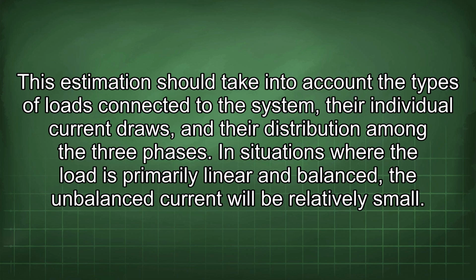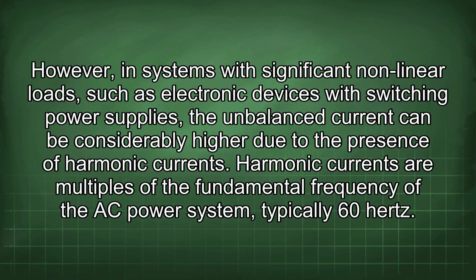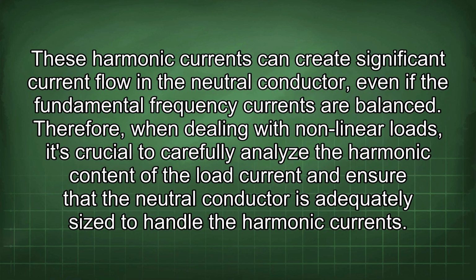In situations where the load is primarily linear and balanced, the unbalanced current will be relatively small. However, in systems with significant nonlinear loads, such as electronic devices with switching power supplies, the unbalanced current can be considerably higher due to the presence of harmonic currents. Harmonic currents are multiples of the fundamental frequency of the AC power system, typically 60 Hz. These harmonic currents can create significant current flow in the neutral conductor, even if the fundamental frequency currents are balanced.